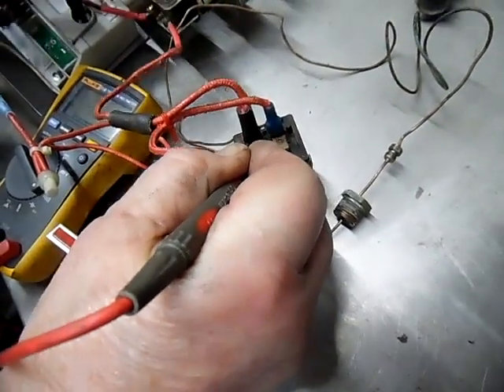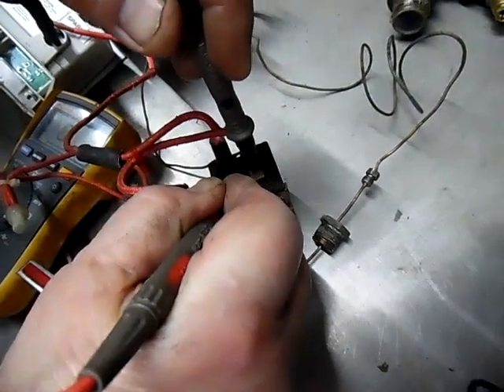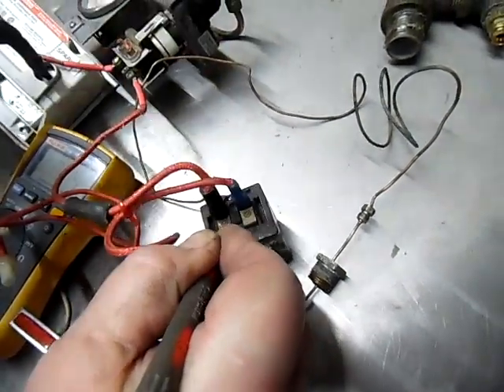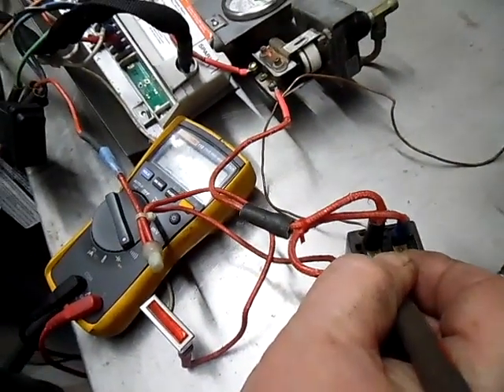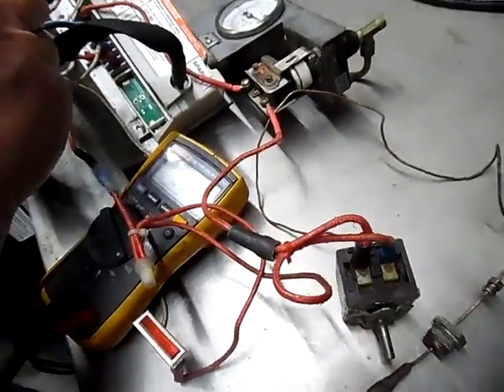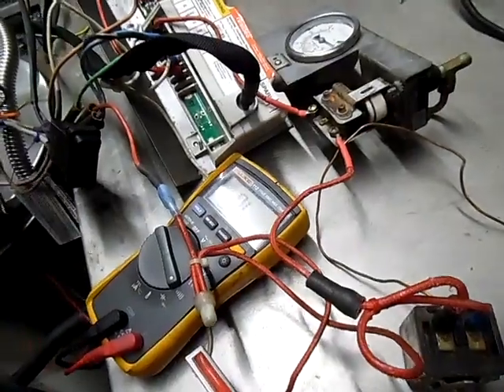So my wire is reading good. I go across the thermostat because the thermostat is on. It's reading. So now I've got continuity all the way to MV. So all I have to do is wait for power to come on this red wire, and this system will come on for the main burner.